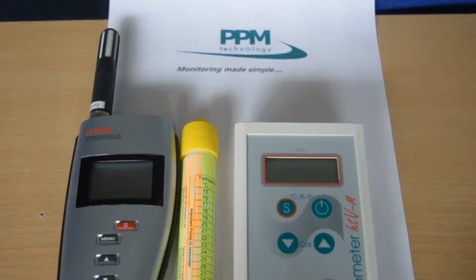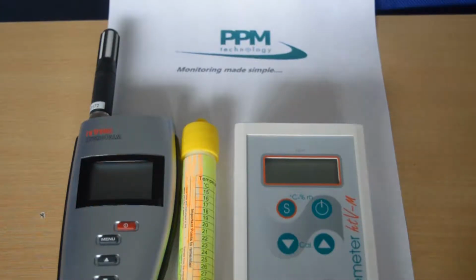Before carrying out a calibration check, the thermometer, the calibration standard, and the instrument were placed together in a location where the temperature was stable for at least 1 hour before commencing the calibration check. This was to allow for thermal equilibration.